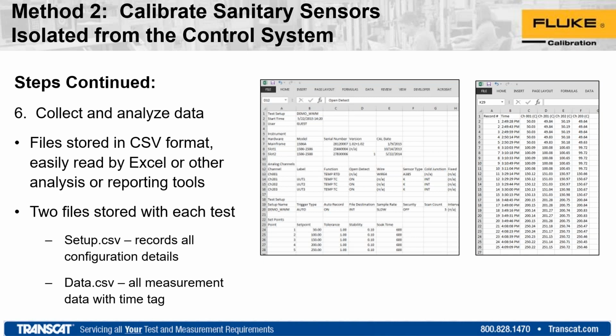So again, the 1586 has a built-in USB. Once everything's run, you can export the files from the testing in CSV format to a thumb drive, and then you can take it over and use some other tool, maybe Excel or something, to analyze the data of what went on during the testing process. So again, this is where things can get a little more involved. For example, if you're using an RTD, and you've got raw resistance data compared to temperature data of the standard, and you're going to recalculate the Callendar-Van Dusen coefficients for the probe and then plug that back into the system, this is where you would take that raw data and run the additional mathematics needed to fit the raw data, in this case resistance, to the temperature.